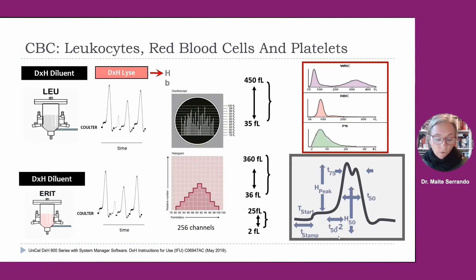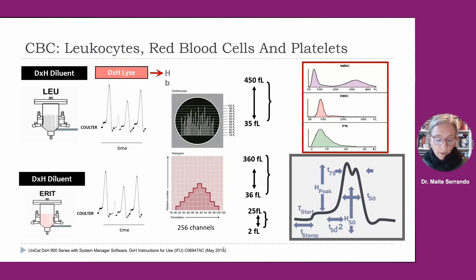Allow me to give you a quick overview of Beckman Coulter technology. The CBC module has three apertures for leukocytes and three apertures for red blood cells and platelet counting, providing the system manager many measurements from electronic pulses, such as time, volume, count rate, wait time, and pulse width.